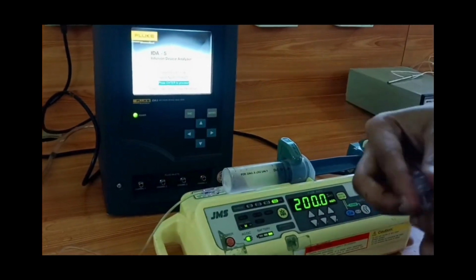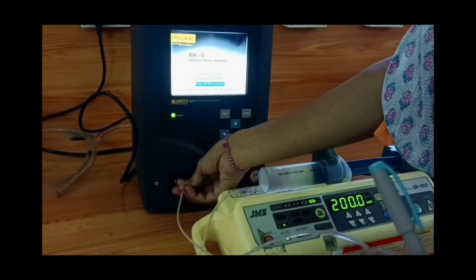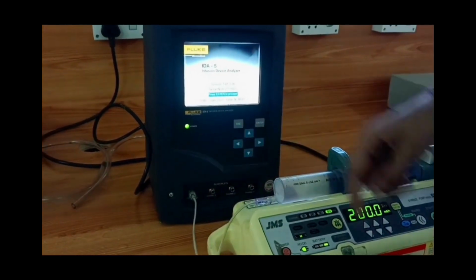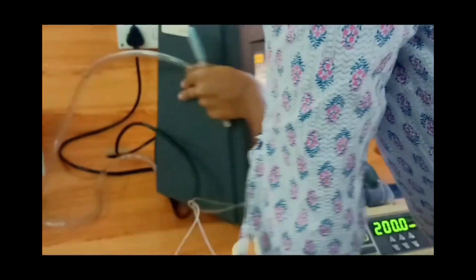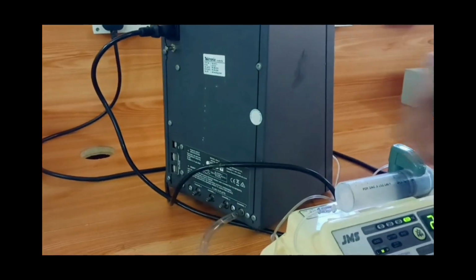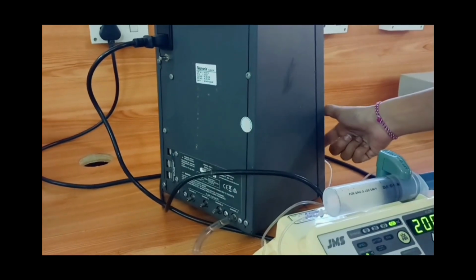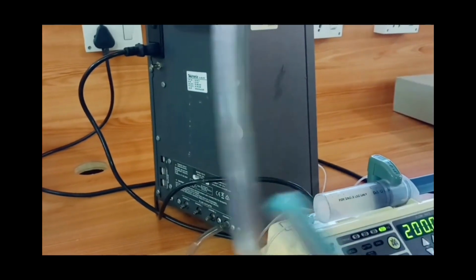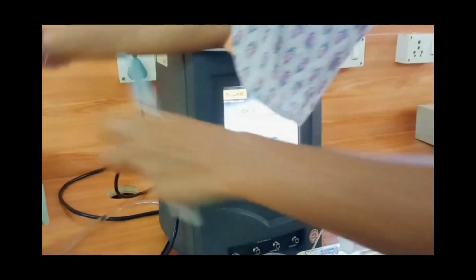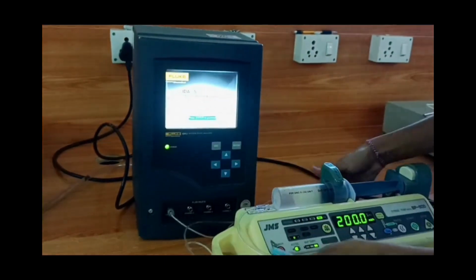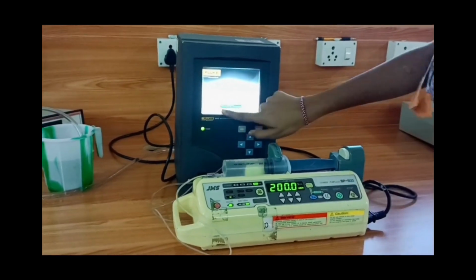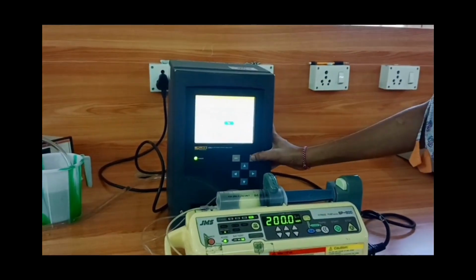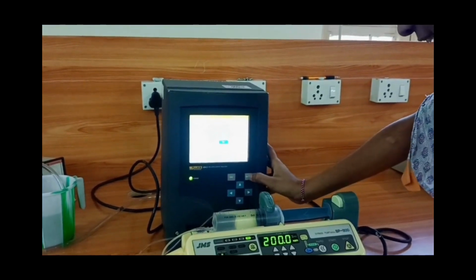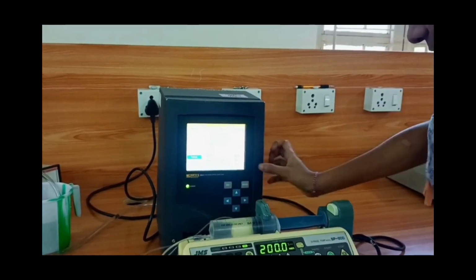The intravenous tubing which is connected to the syringe must be connected to this calibration device, to the channel which we are using. After that, at the back side of the infusion device analyzer, whichever channel we have selected in front, to that channel only we must connect another tube. Press enter to proceed. After this, now it is set up.